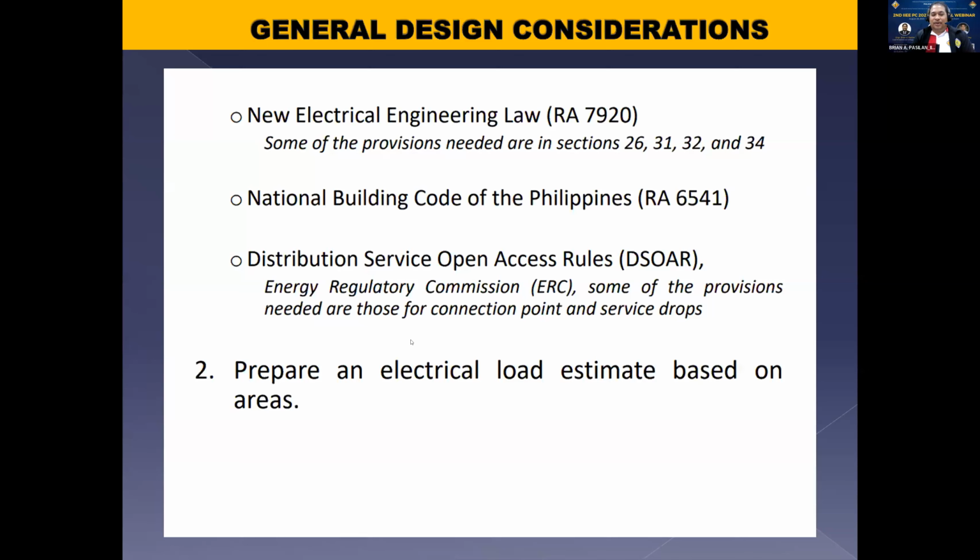So we can now prepare an electrical load estimate based on area. So what we call the load density method, no? Kung wala pa tayong actual loads na nakuha, no? So we have a best practice na set, based on square area, based on the type also of occupancy, no? For a certain type of occupancy, meron yang recommended or established load density per square area.